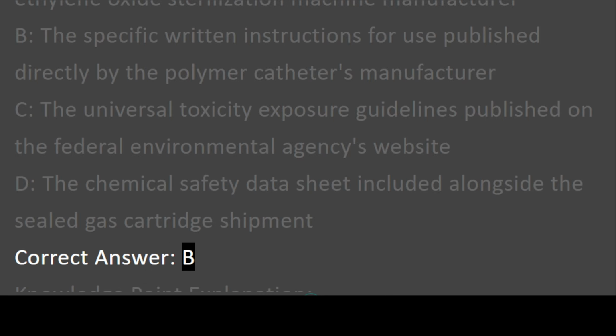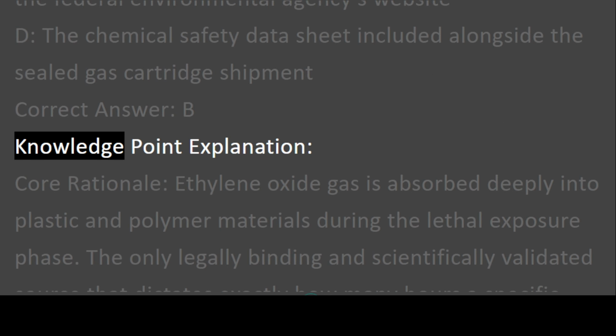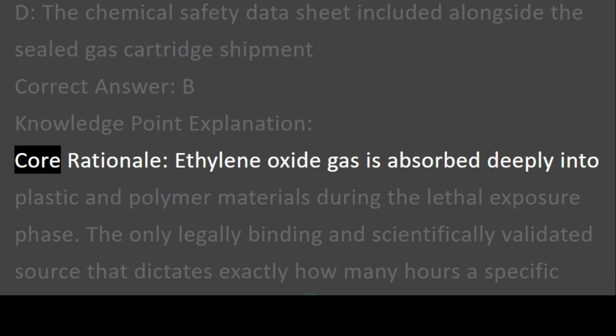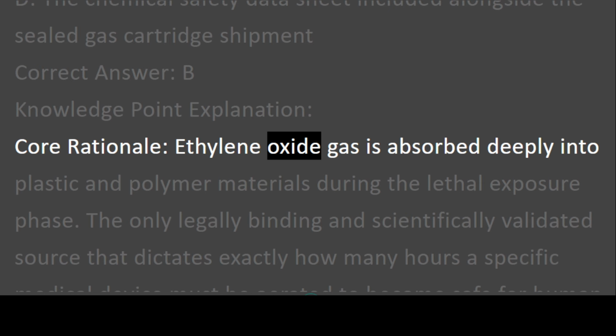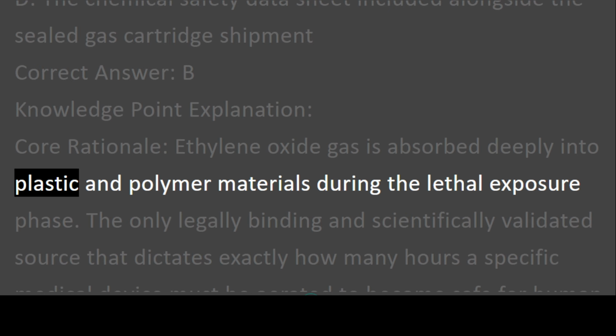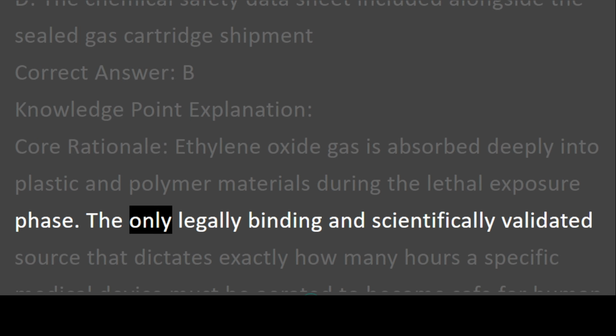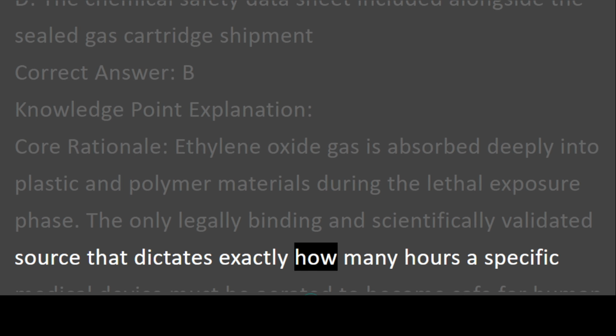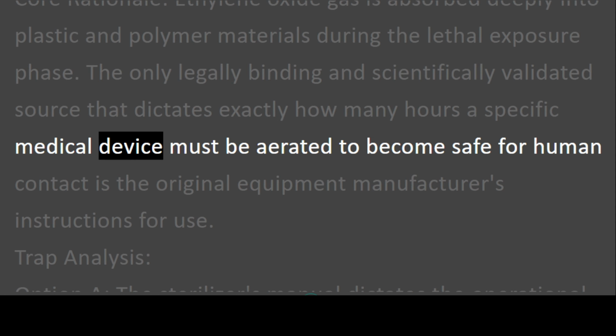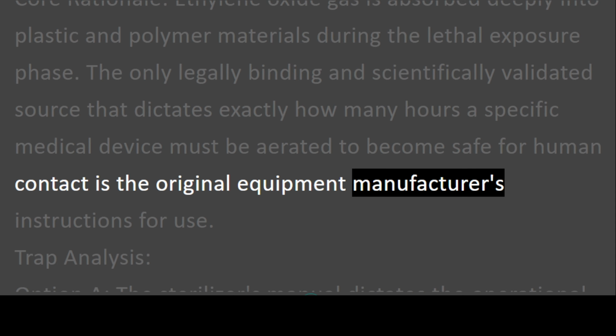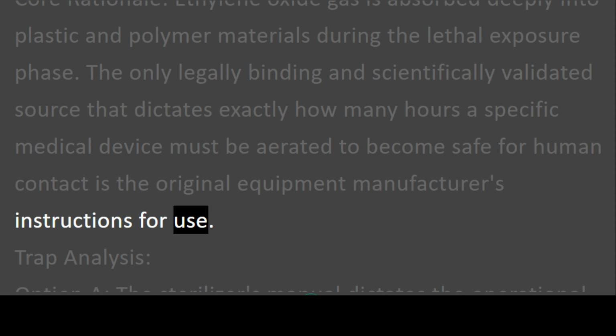Correct answer, B. Knowledge point explanation. Core rationale. Ethylene oxide gas is absorbed deeply into plastic and polymer materials during the lethal exposure phase. The only legally binding and scientifically validated source that dictates exactly how many hours a specific medical device must be aerated to become safe for human contact is the original equipment manufacturer's instructions for use.